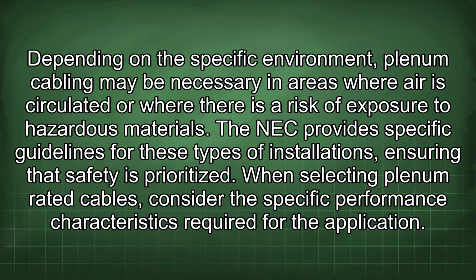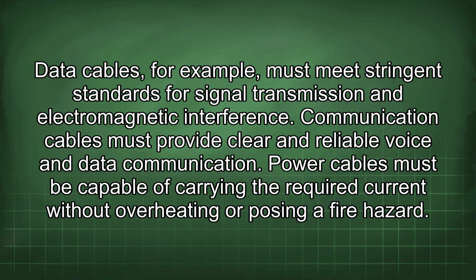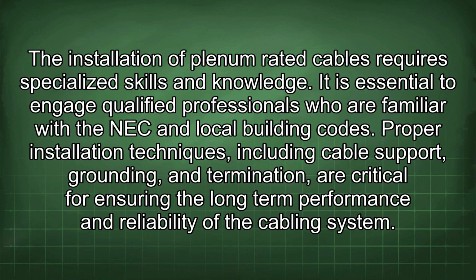When selecting plenum-rated cables, consider the specific performance characteristics required for the application. Data cables, for example, must meet stringent standards for signal transmission and electromagnetic interference. Communication cables must provide clear and reliable voice and data communication. Power cables must be capable of carrying the required current without overheating or posing a fire hazard. The installation of plenum-rated cables requires specialized skills and knowledge. It is essential to engage qualified professionals who are familiar with the NEC and local building codes.